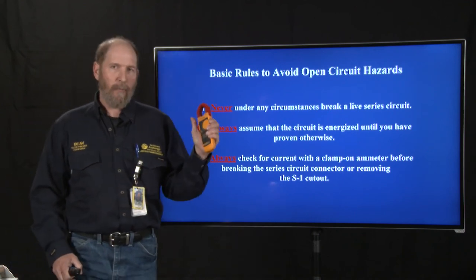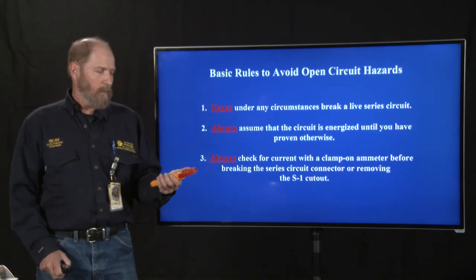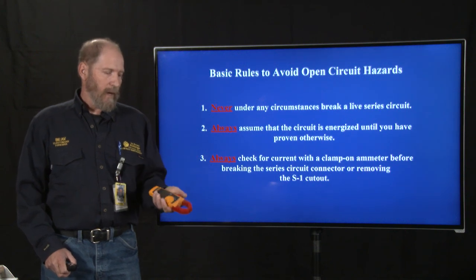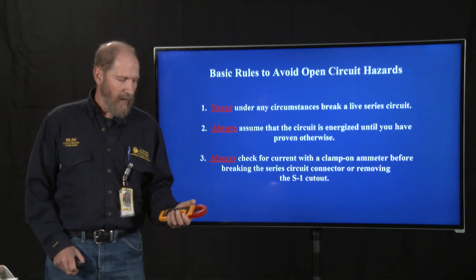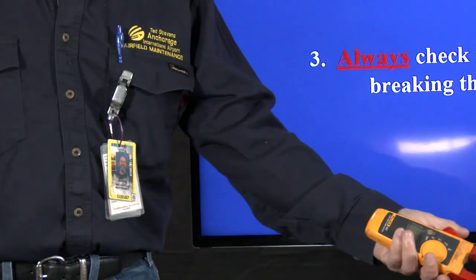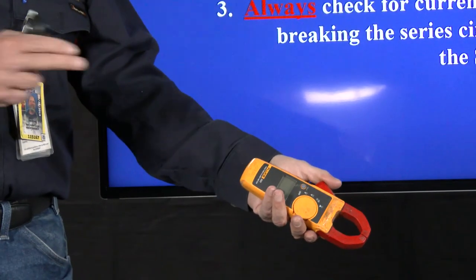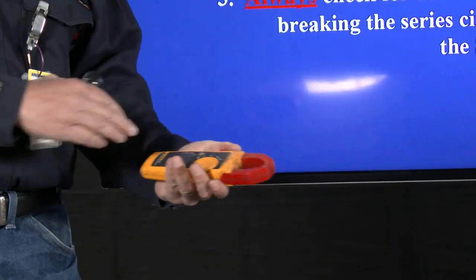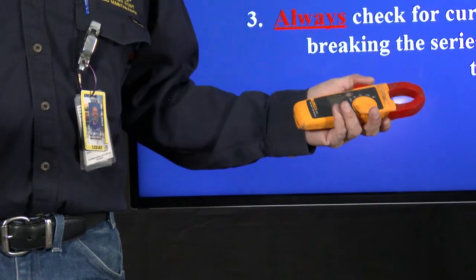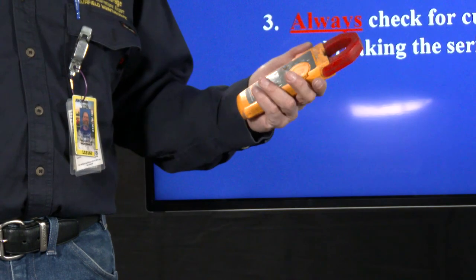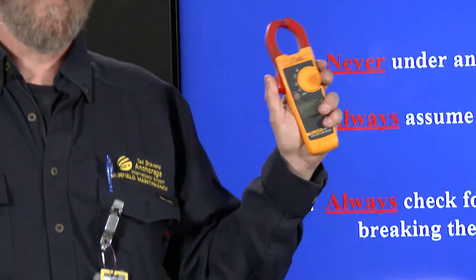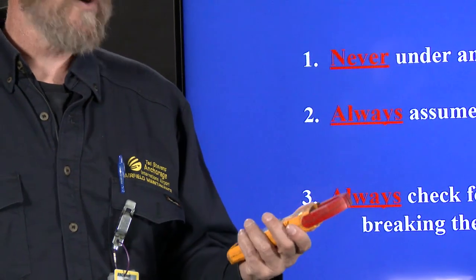Now this is your amp or clamp-on ammeter. If you clamp it on, turn it to amps. If there's any flow in that wire, it should show. If it shows zero, it should be good to open up your circuit. Do you know your ammeter is working or not? It's important to know that.